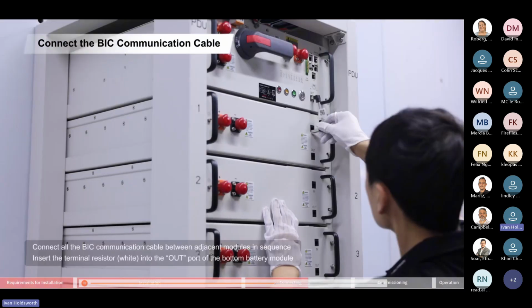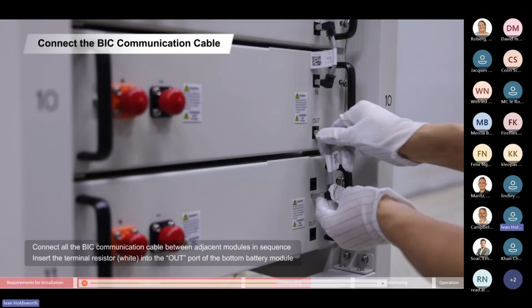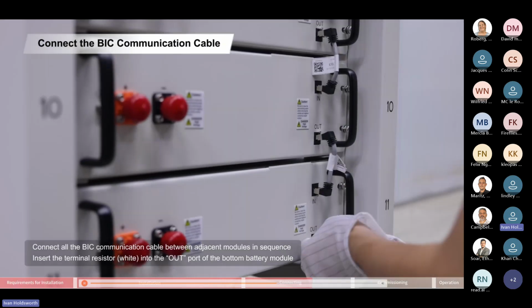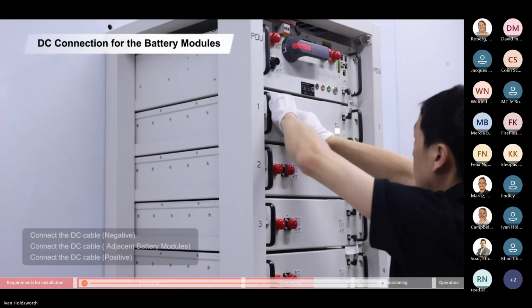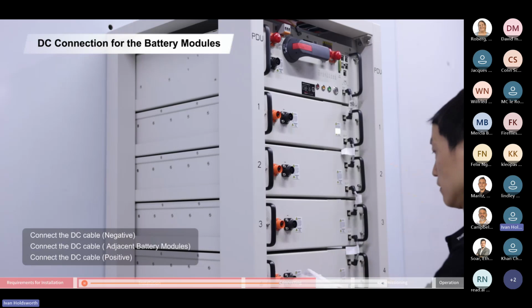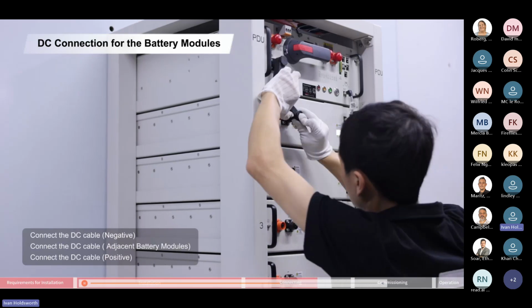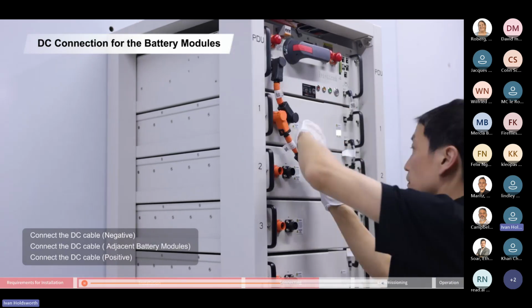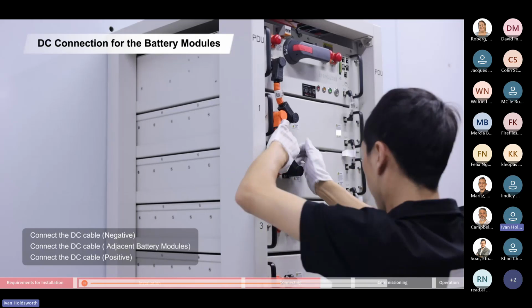It's very important that the PDU and the modules are earthed. The earth connections happen automatically through the chassis of the frame, so you don't have to connect the little earth connections between each module if you're using an official BYD Max Lite frame.